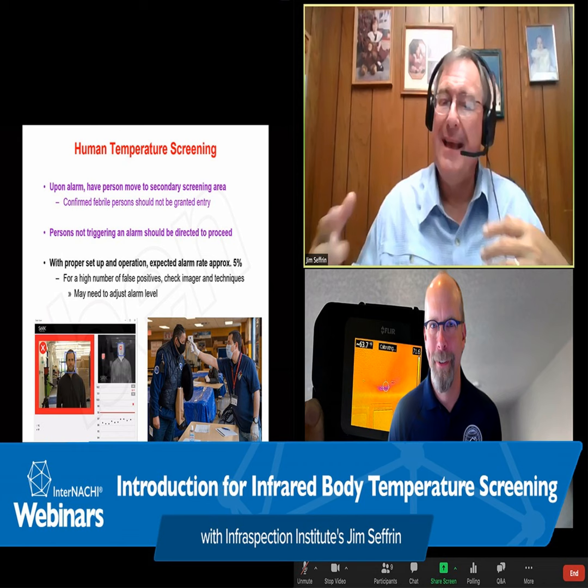It must be understood from the outset that data from an imaging radiometer alone are not conclusive. Therefore, observed temperatures must be confirmed by independent means in order to meet the protocols set forth by the FDA and the International Organization for Standardization, or ISO.